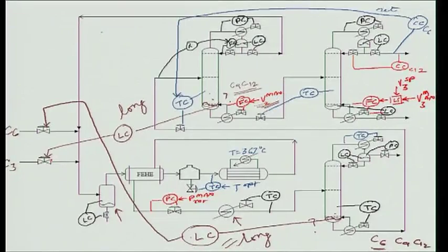So, it is a very simple scheme, with no alteration of the material balance control structure depending on which constraint is active and which constraint is not active. Regardless of where you are operating, regardless of what throughput you are at, the basic inventory management scheme remains the same. So that is that. I think this case study brings out the contrast between the conventional pairing approach and the economic plant wide control approach that we are proposing. So I think that takes care of that.